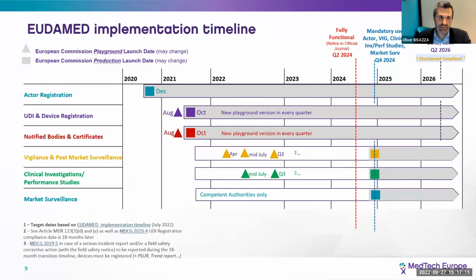The purpose of this slide is now just to tell you that there are many different modules to the database: actor registration, UDI and device, notified body certificates, etc., etc. The Commission is building the database module by module. And some of them, like the actor registration module, work on it started quite early, and it's more or less ready to go, I understand. There are others, like the module on clinical investigations and performance studies, which started later and is known to be particularly complex. And that's why you see, I think, these delays in delivering EUDAMED. EUDAMED is only considered live and ready to go when all modules are live.